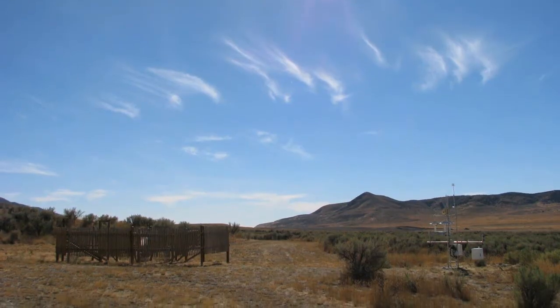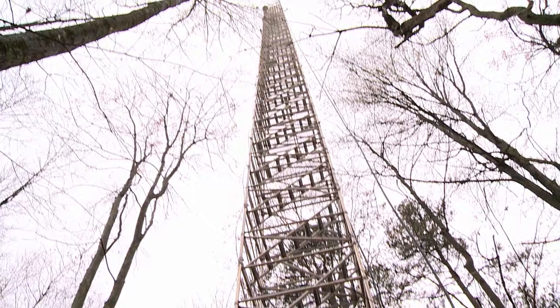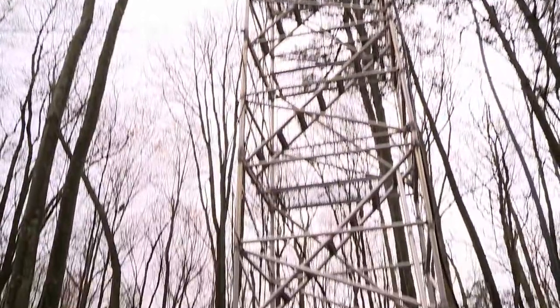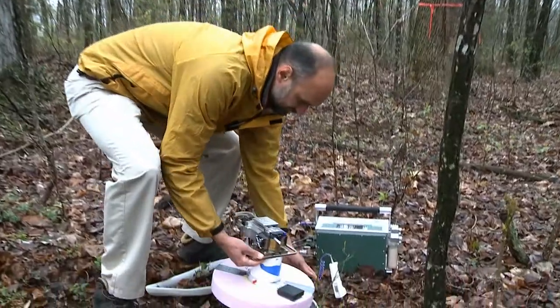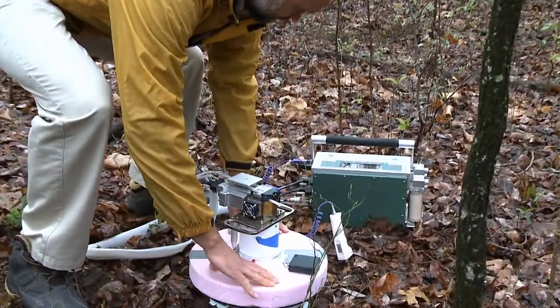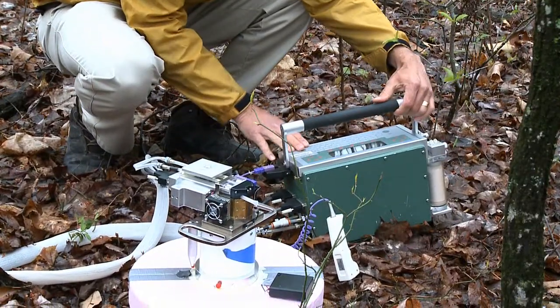The locations of these sites and these networks were meticulously chosen to be in areas that would accurately represent the area. All of our sensors are calibrated against NIST traceable standards, and the primary measurements have triple redundancy in order to assure confidence and completeness of the data record. Careful design and planning of the measurement systems have yielded data recovery rates that exceed 99%. A constant challenge with our research is getting the best measurement possible. A reliable, accurate measurement assures scientific integrity.